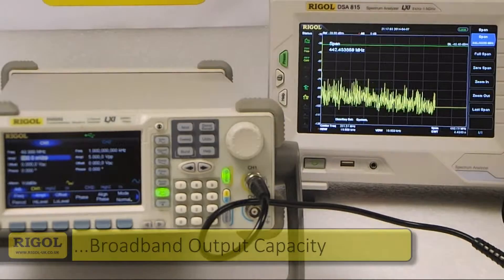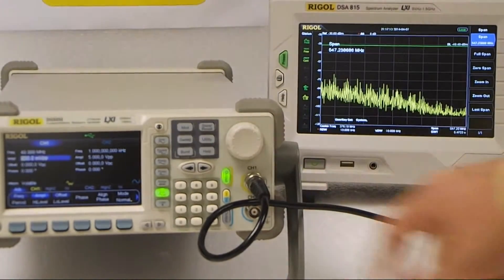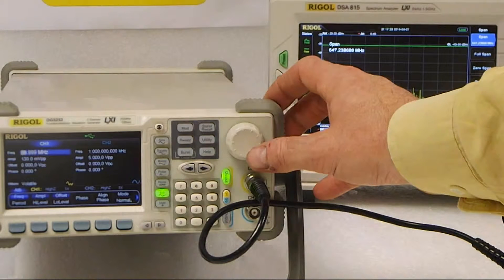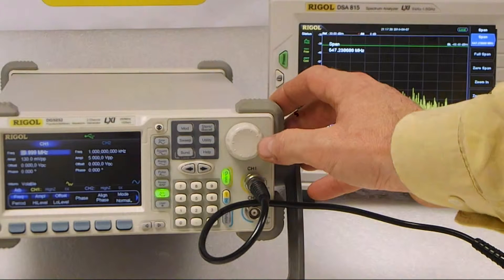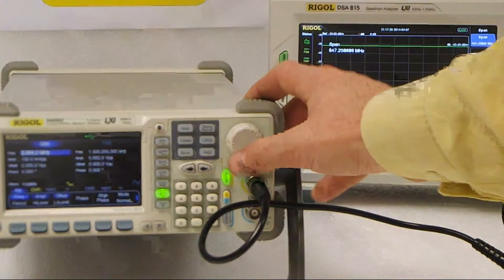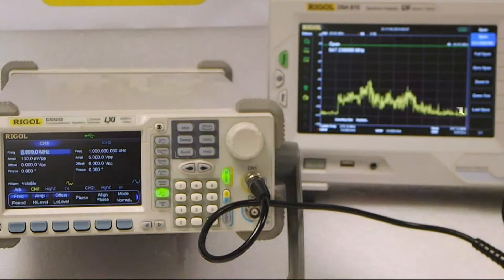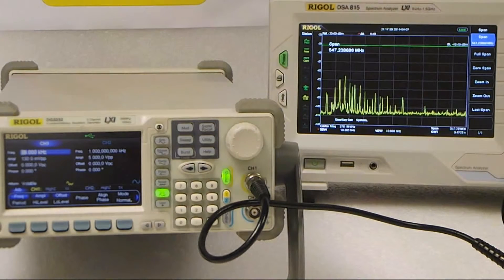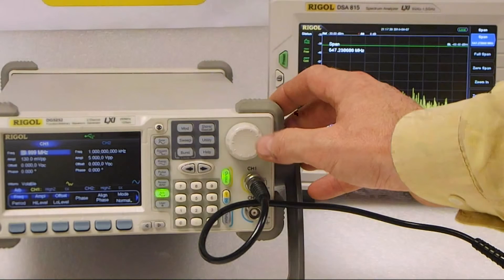For all different frequencies of DG series the output capability of the amplifiers is the same — extremely capable of broadband output. I'm going to slow down the frequency of the arbitrary waveform so you can see that it breaks up into regular spectral sections. The arbitrary waveform is being played at a much slower rate and a more regular spectral pattern with bands of signals starts to appear. The arbitrary waveform in this case is 100 points long, so there will be a regular pattern caused by playing it back less frequently. Even playing it at 9 kHz it has extremely broad spectral content — these tests indicate just how capable the DG5000 is.